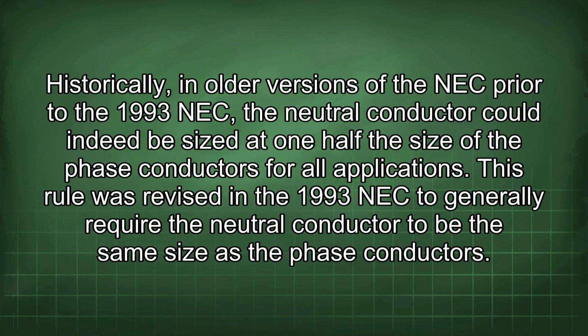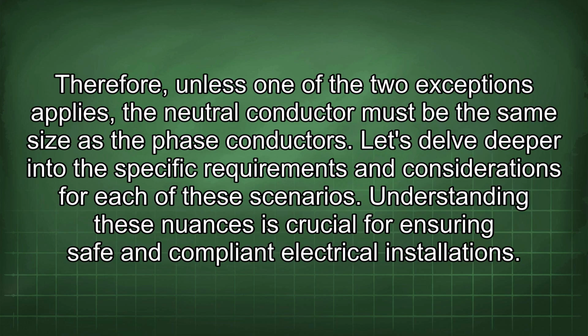This rule was revised in the 1993 NEC to generally require the neutral conductor to be the same size as the phase conductors. Therefore, unless one of the two exceptions applies, the neutral conductor must be the same size as the phase conductors. Let's delve deeper into the specific requirements and considerations for each of these scenarios. Understanding these nuances is crucial for ensuring safe and compliant electrical installations.